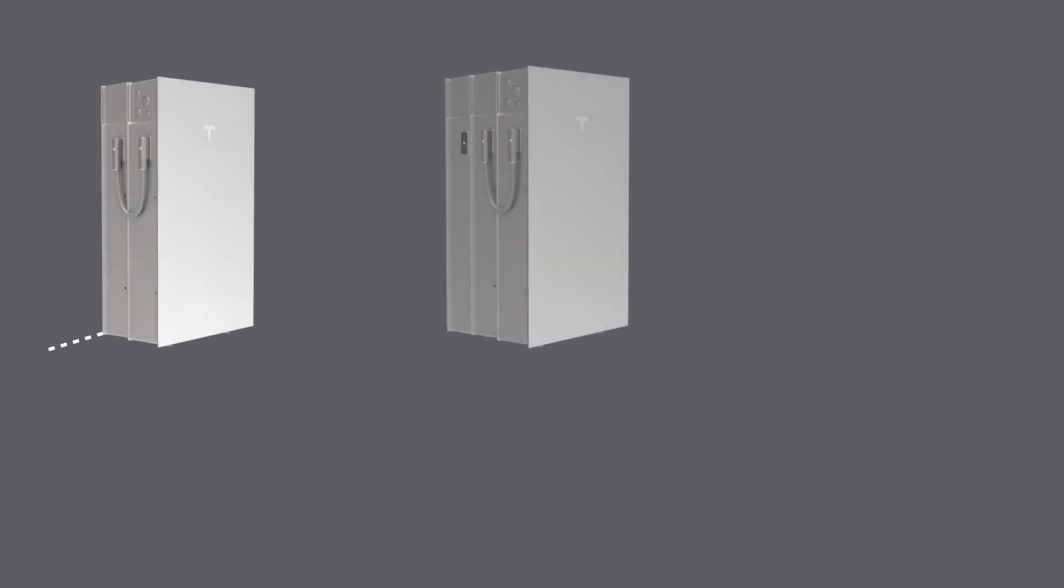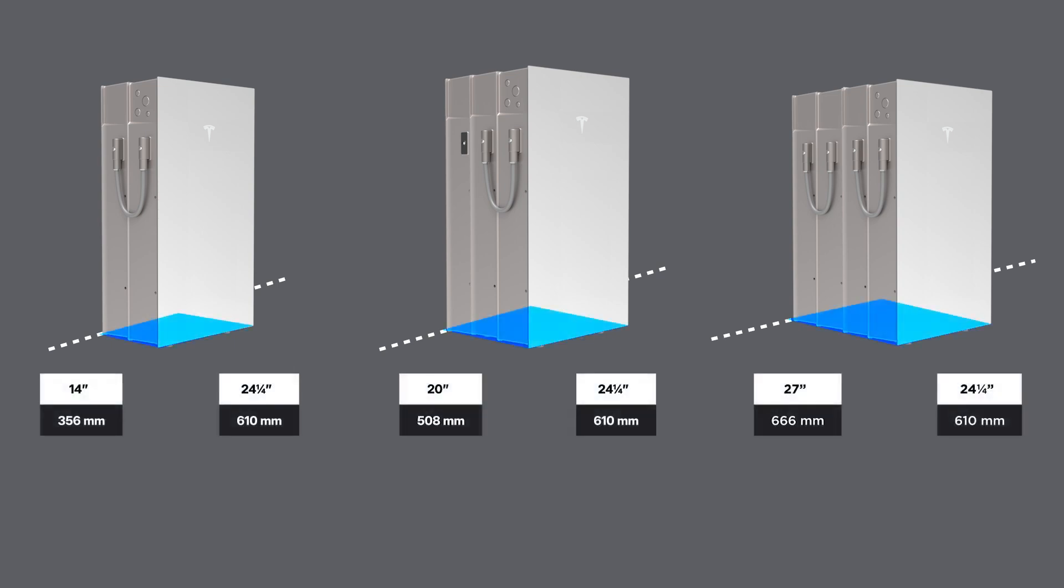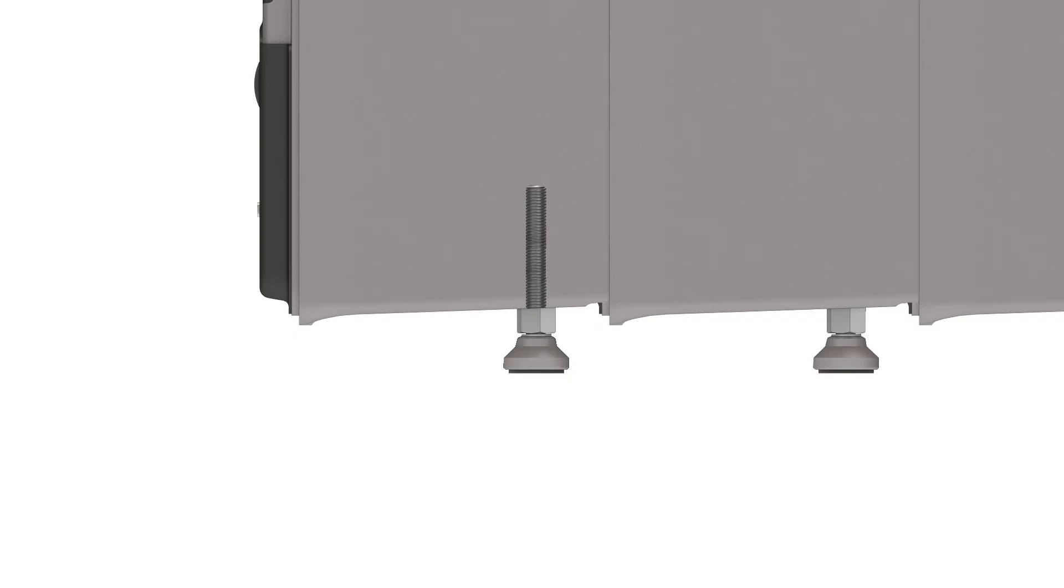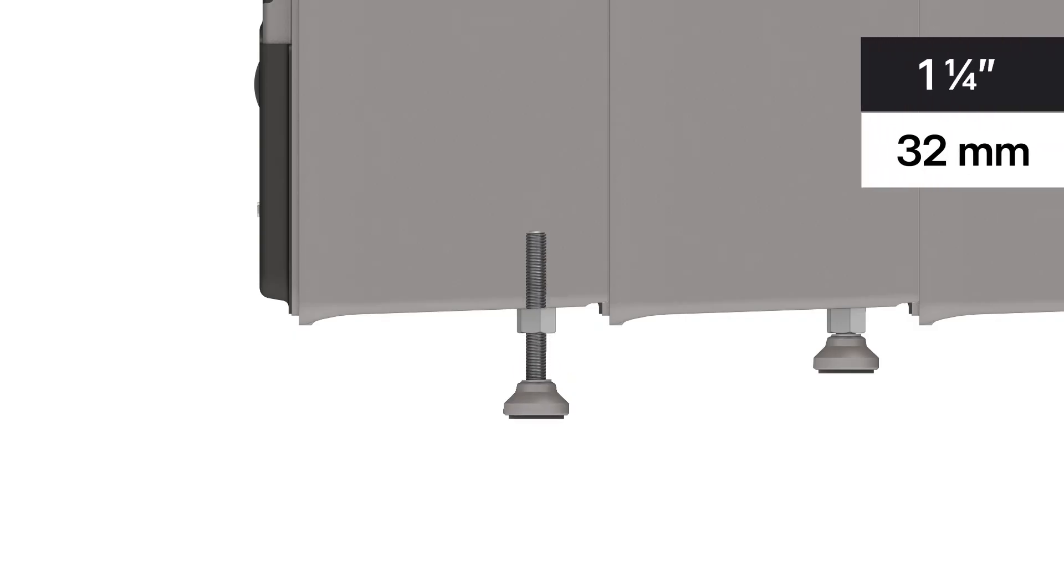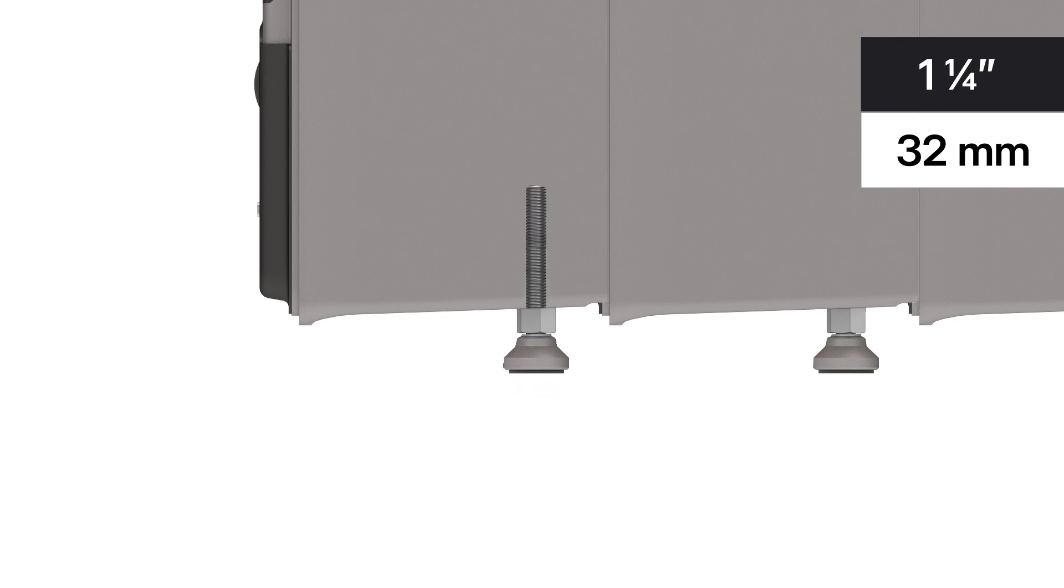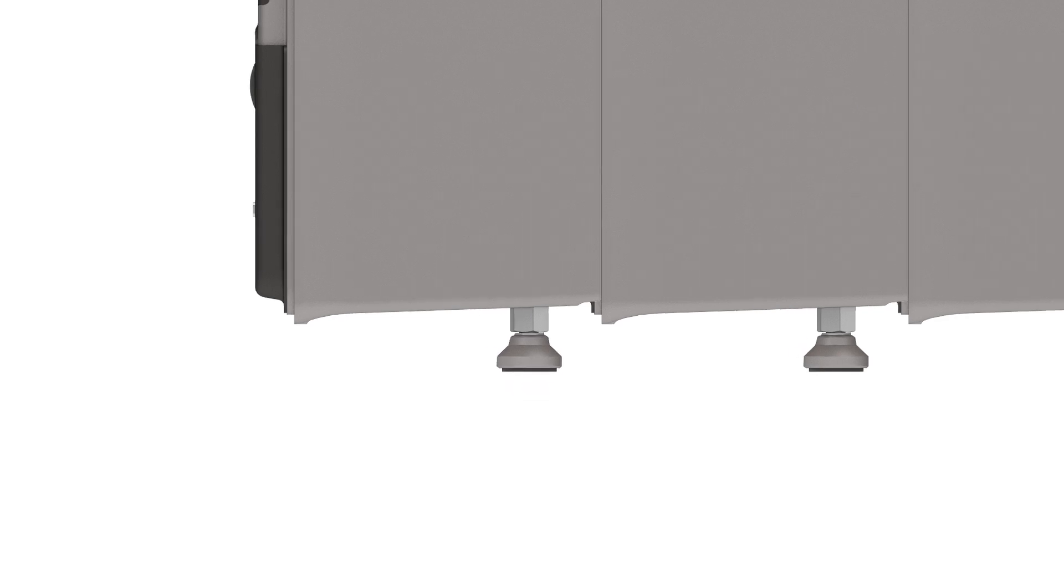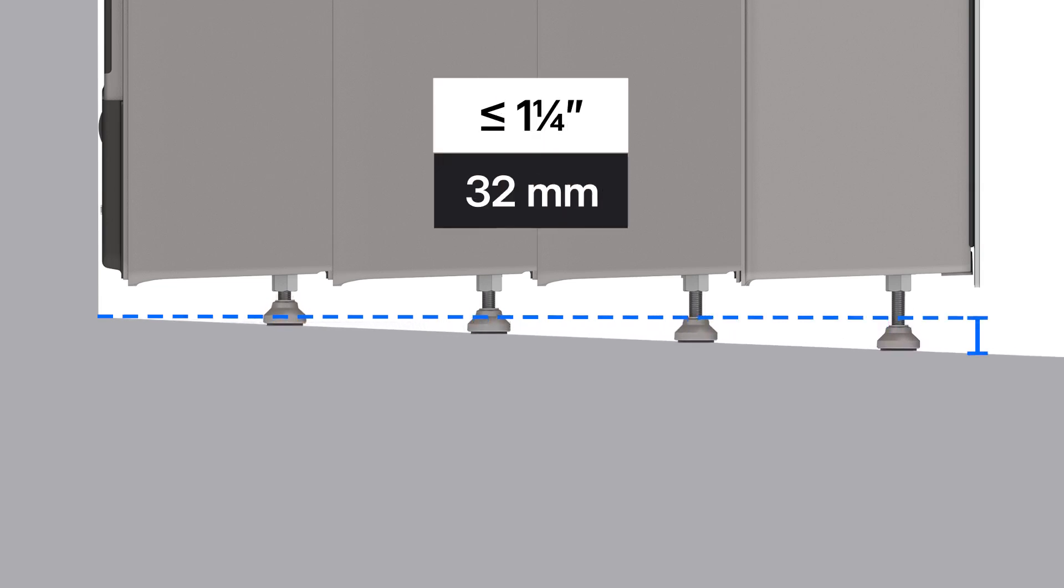Before mounting the first expansion unit to the wall, it is critical to assess the floor where the stack will be mounted to ensure that it is compliant with the Powerwall stacking requirements. The feet on Powerwall can be adjusted up and down by the maximum amount shown here. Keeping that in mind, the slope of the floor will need to be assessed to ensure that the lowest point of the stack will be within this range.